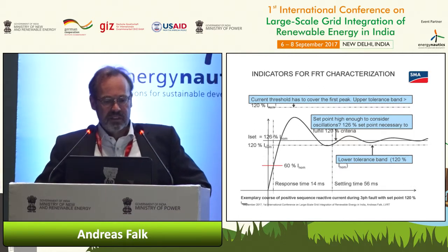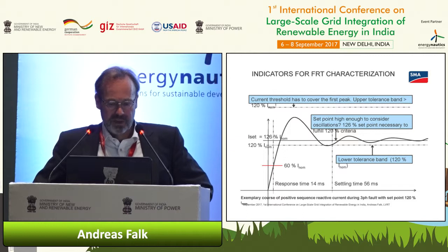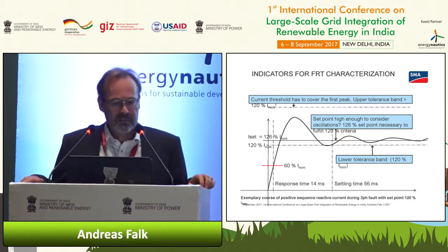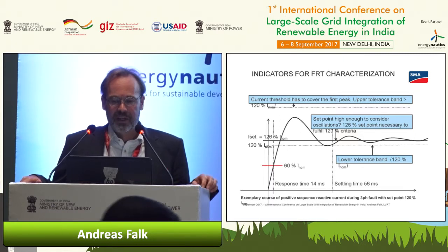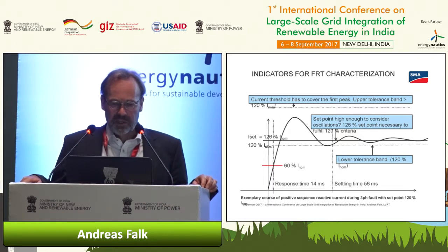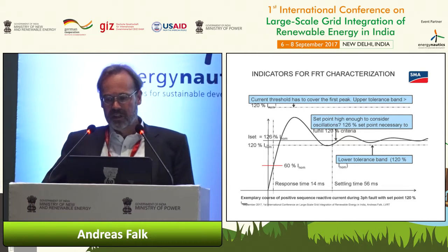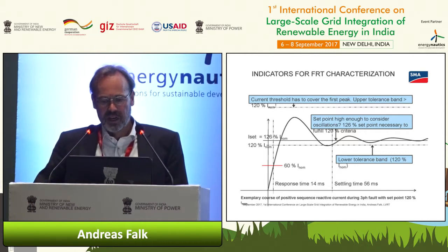And what you can see is you have a response time, in that case 14 milliseconds. And then you have something like an overshoot because the control cannot react fast enough. And then you have an oscillation until the final FRT current is reached.